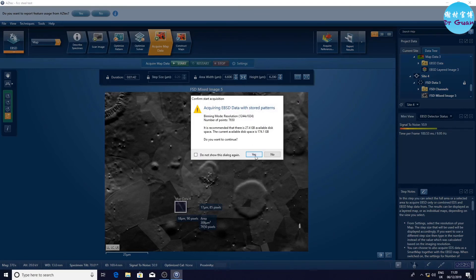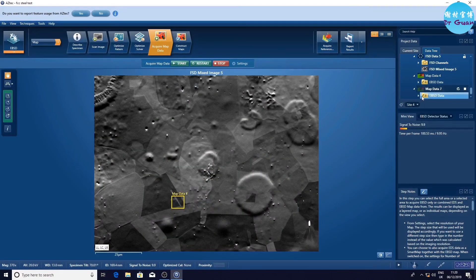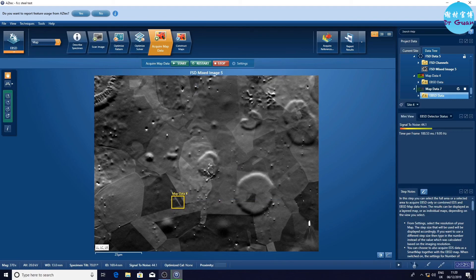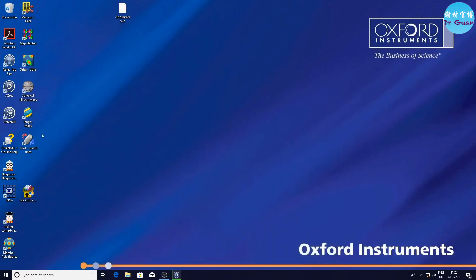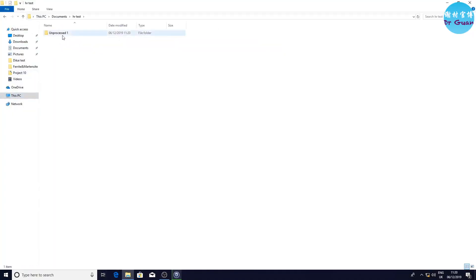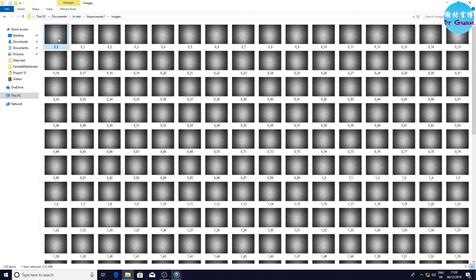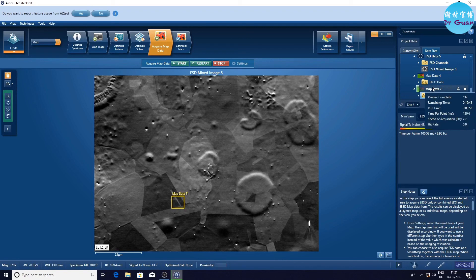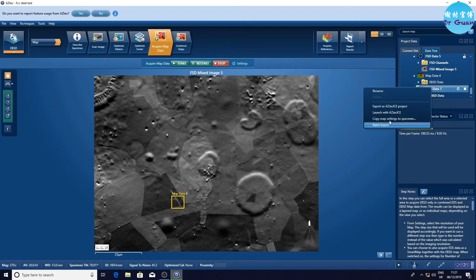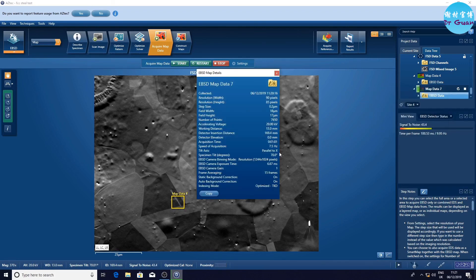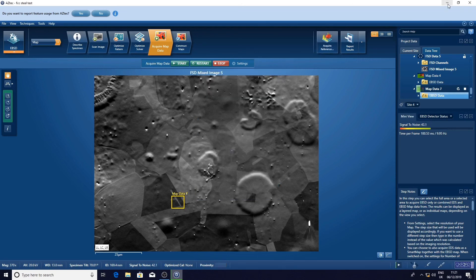We just check the details. It's 10 points per second. It's going to be 15 minutes. Now we are going to check the saved Kikuchi patterns, the raw Kikuchi patterns. That's all here. It's going to be 15 minutes, nearly 16 minutes. You can check the speed of acquisition has been decreased because the saving speed, this image saving has decreased the time, and some other factors as well.